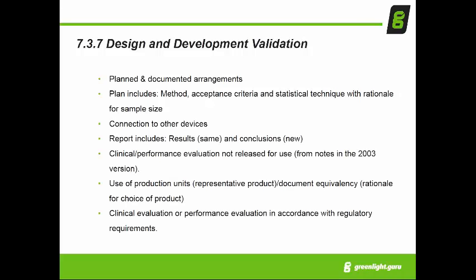Design and development validation, you're going to see a lot of similar language. Again, verification is demonstrating that your design and development outputs meet your design and development inputs. Design and development validation is demonstrating that the product meets your user needs. So there's a lot of similarity between verification and validation. This is an area where that clinical definition I talked about, one of those key definitions that changed, has an impact.